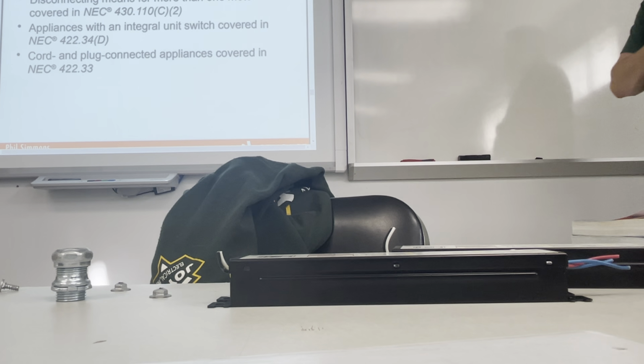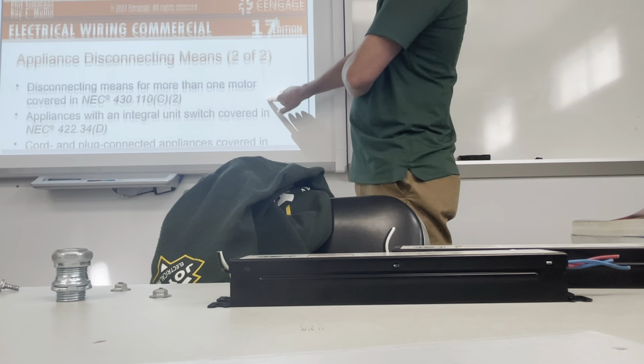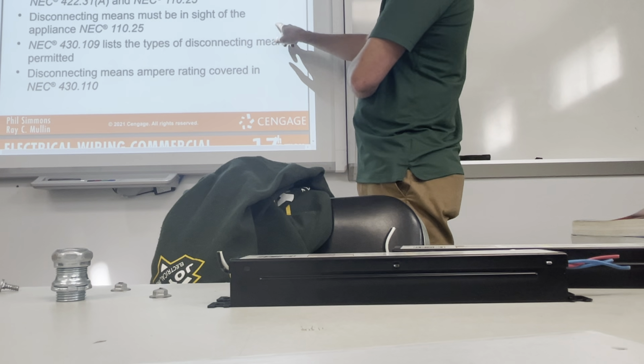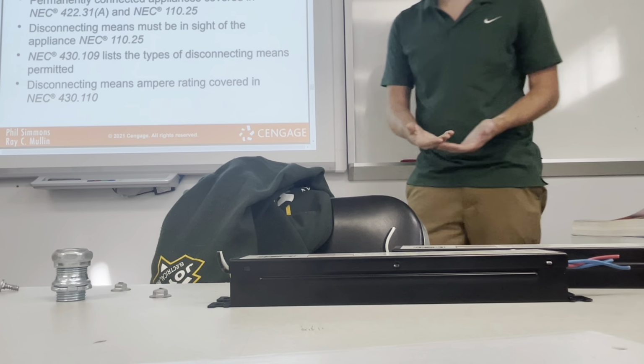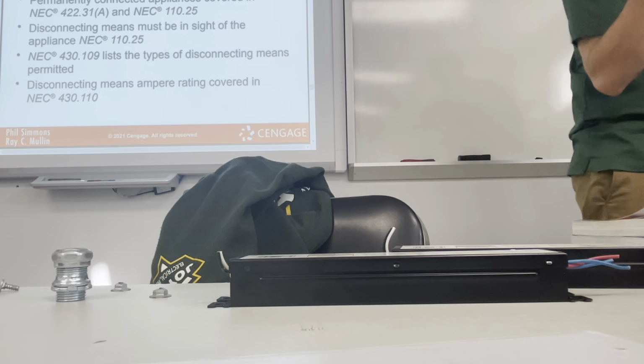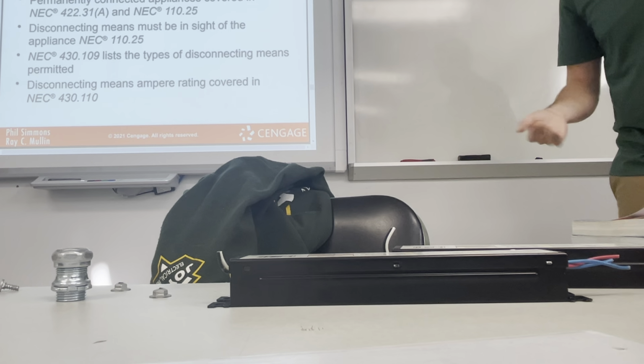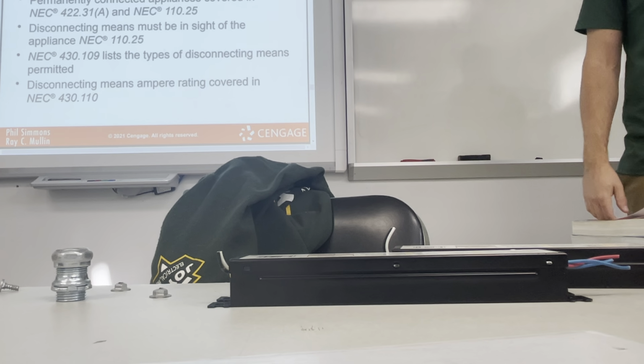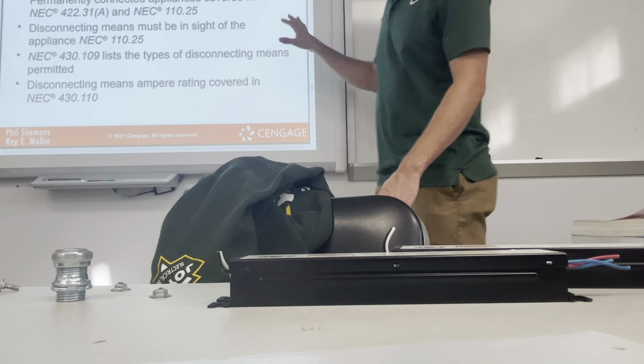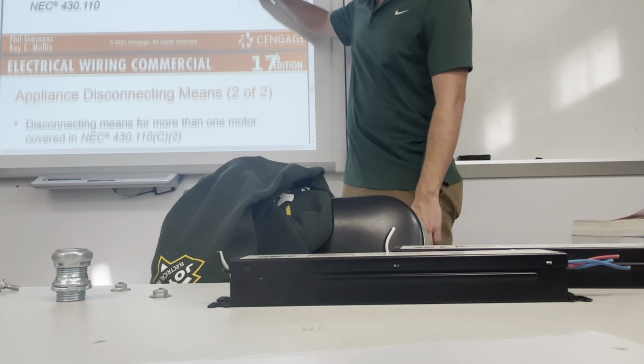Disconnecting means for more than one motor is covered in NEC 430.110(C)(2). Appliances with integral unit switch are covered in 422.34(D). Cord and plug connected appliances are covered in 422.33. All right, so when it gets down to this, once again, just dealing with the motors and dealing with appliances, if it's hardwired, the disconnect has to be visible within line of sight of that unit. If it's plug-in, that's usually your disconnect. All right, so once again, the disconnect applies to hardwired situations only.